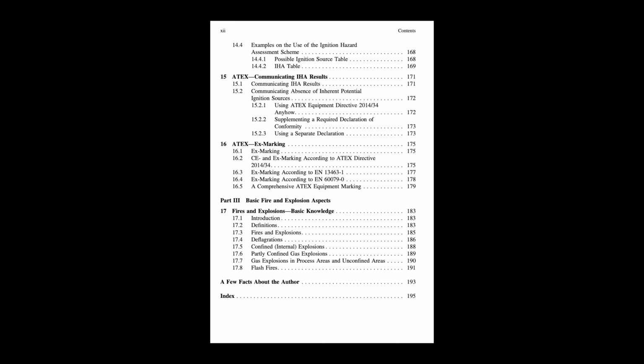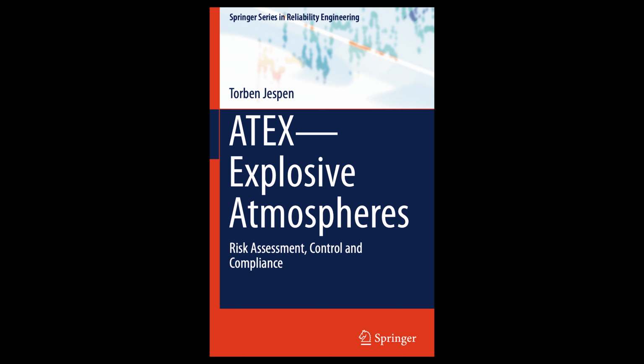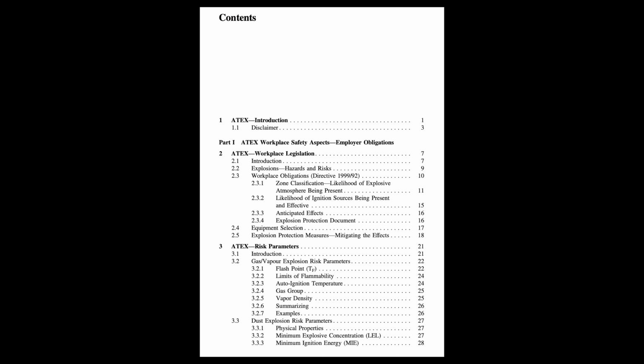With very good ventilation and low pressure, the hazardous zone might be deemed negligible extent, or NE, meaning it's so small you don't need specially protected equipment right there. So ventilation is key for natural gas zones, too. Absolutely. The guide also introduces the concept of calculating the hazardous volume, V, based on release rate and ventilation effectiveness, although it notes these standard calculations can be quite conservative compared to, say, CFD modeling. Computational fluid dynamics. Right? Computer simulations of airflow and gas dispersion, which can give a more detailed picture.